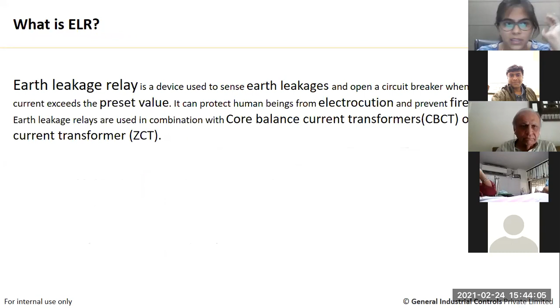Now let's take a situation where we have two systems: one where ELR is not used, and one where ELR is used. Let's take the case where ELR is not used. The person is directly in touch with the motor, and because of some issue, let's say there is no proper insulation, the leakage current will get generated and pass through the body of this person. So this is going to damage the machinery as well as the person. But if we are using ELR, then if any issue happens with the motor, it is going to trip the system from here. So ultimately our machinery is safe and the person is also safe. This happens with our device, which is ELR.